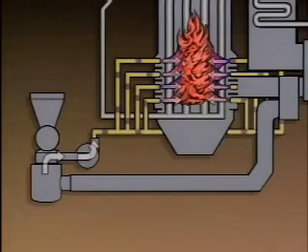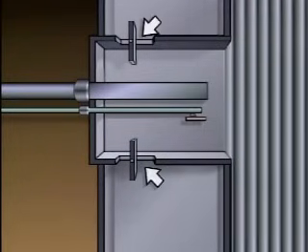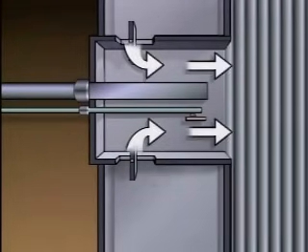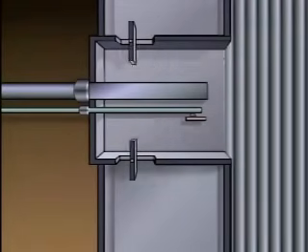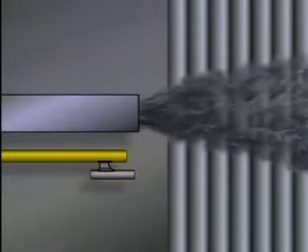The coal and primary air enter the burner through the fuel nozzle and mix with secondary air. The secondary air enters each burner from the wind box through the burner air registers. The registers cause the secondary air to swirl around, adding to the turbulence caused by the fuel nozzle. The heat needed to start combustion comes from an igniter. One common type of igniter used in coal-fired boilers consists of a miniature oil burner that can be lit by a device similar to a spark plug.